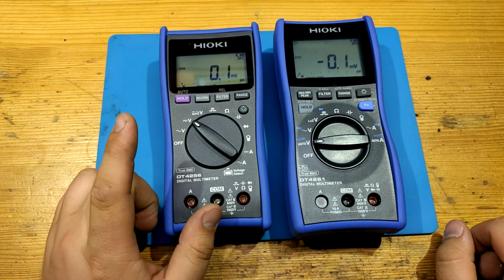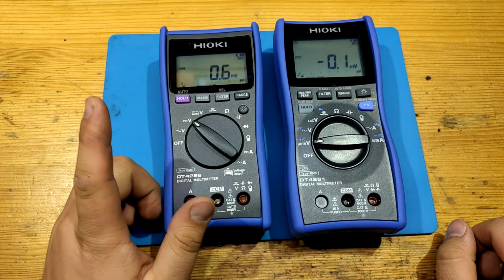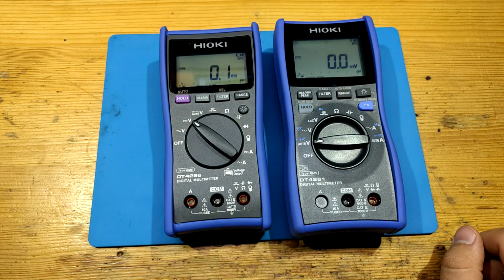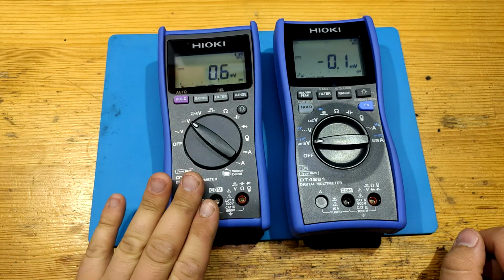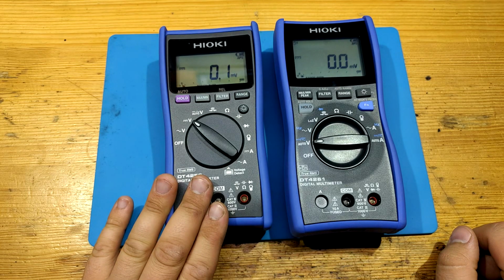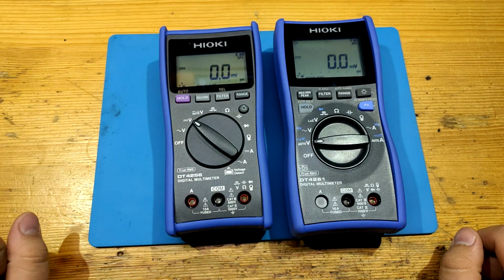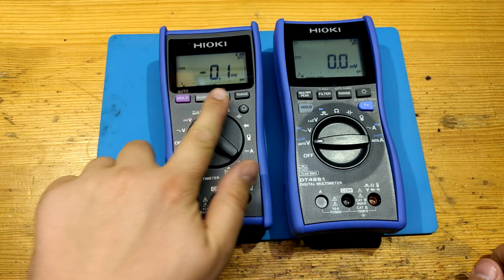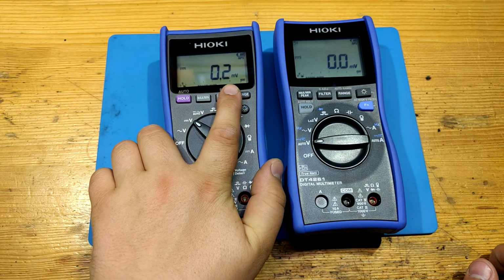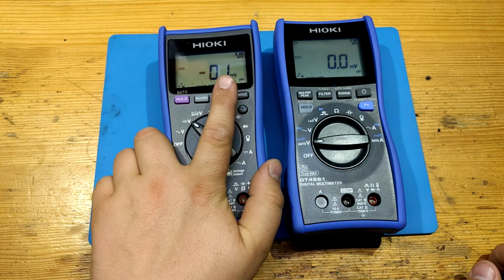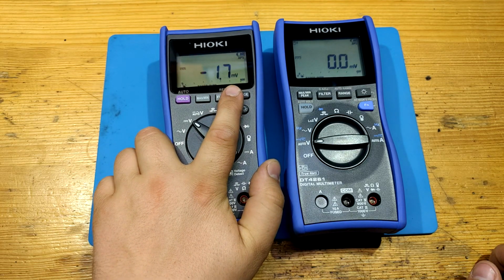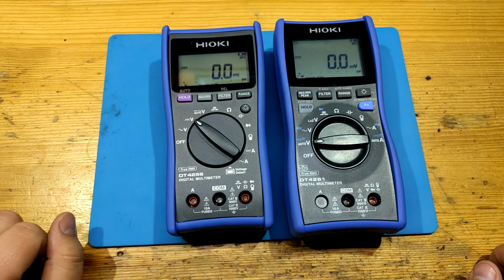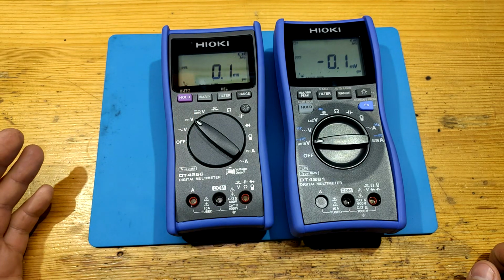So considering my approximation, the real error would be around 0.0083%. That would make them fall into 0.01% accuracy. The 4256 is 30 times more accurate than what it claims to be. The display is the only limit here. If we had one more digit, the last one, we could get an even better number. I would recommend putting more digits displays in their equipment. 5 is okay for such a multimeter, like for example 22,000 counts at least.